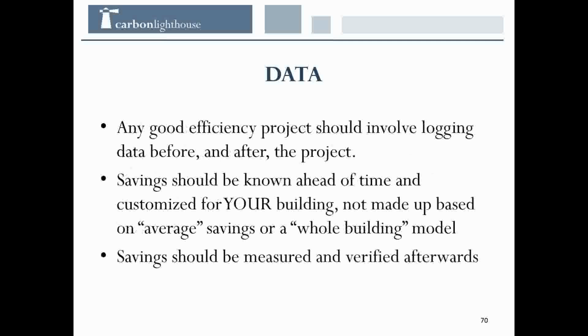Savings should be known ahead of time and customized for your building or client, rather than saying on average variable frequency drives save 30%, which may be true, but needs to apply to that particular building. At the flooded building, for example, the VFD was not going to save 30% - it was going to save nowhere near enough to justify its cost. So making sure your savings predictions are specific to your building is really, really key.